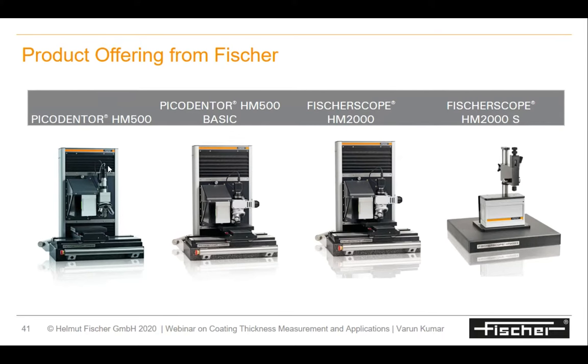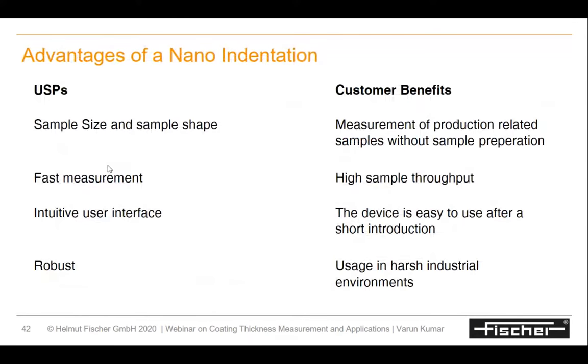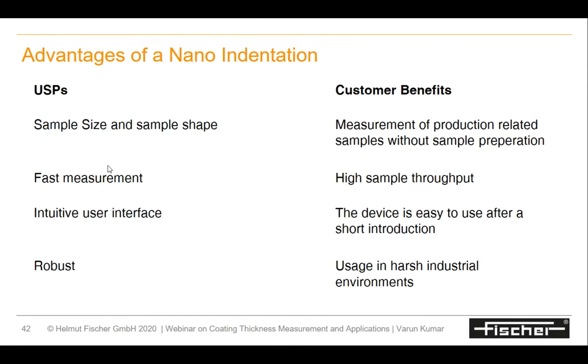Nano indentation products include the Pico Indenter and Pico Indenter Basic for R&D and research purposes, with an option to attach an AFM for better imaging of the indentation. The HM2000 is more suited for the paint industry to find physical and hardness properties of paint, and for bulk material where a reference hardness value of coatings is needed. The device is easy to use after short training and is designed for harsh environments.